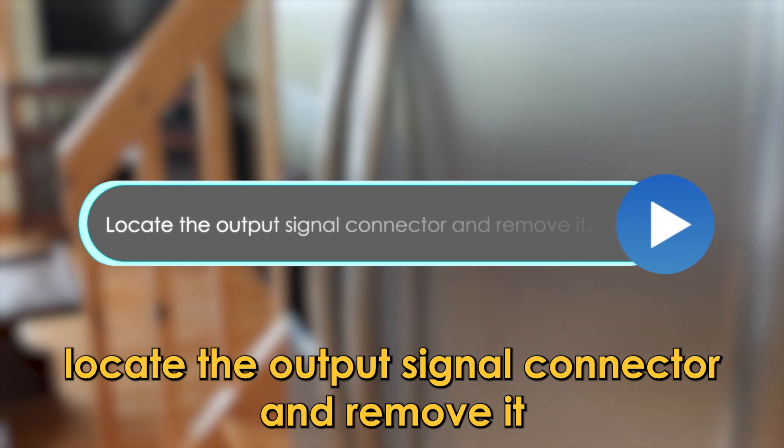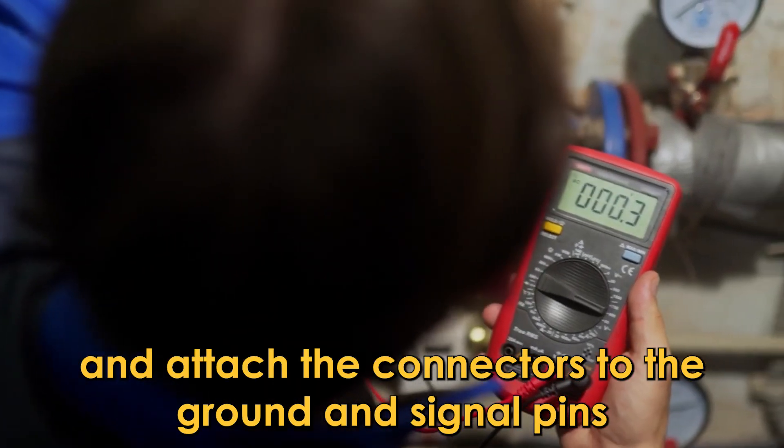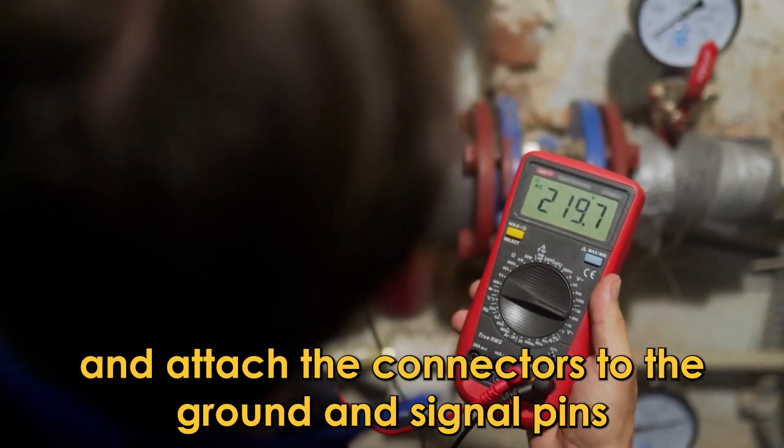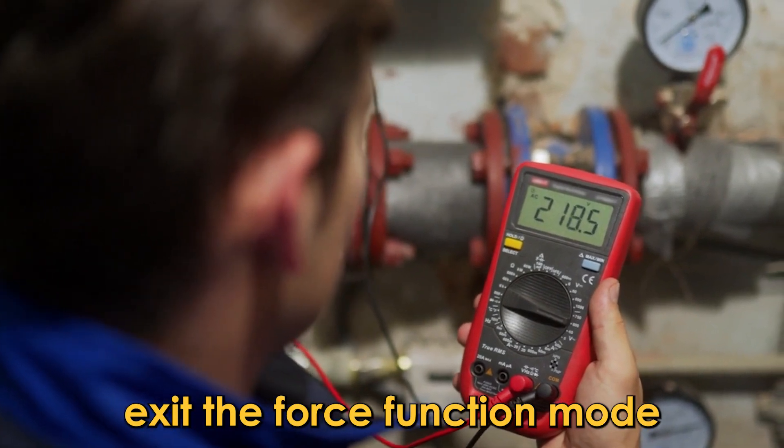Locate the output signal connector and remove it. Set your multimeter to DC and attach the connectors to the ground and signal pins. If you don't get a voltage reading, replace the control board. Exit the forced function mode.